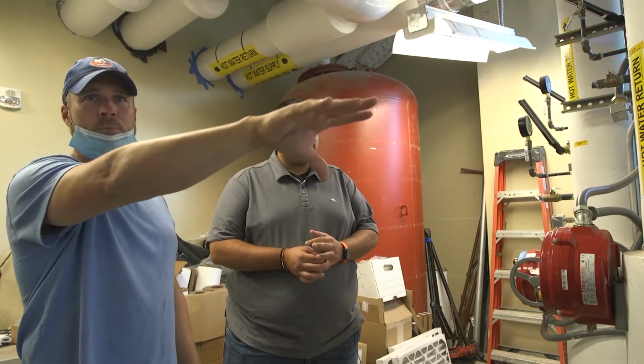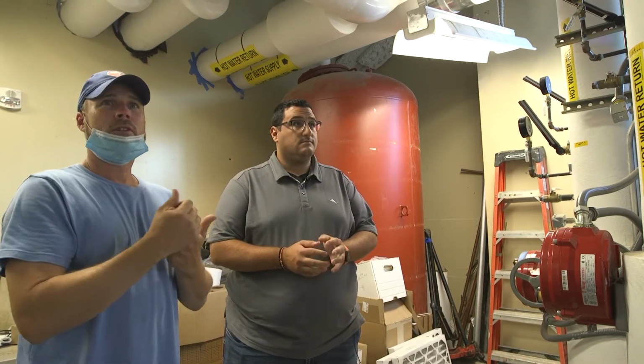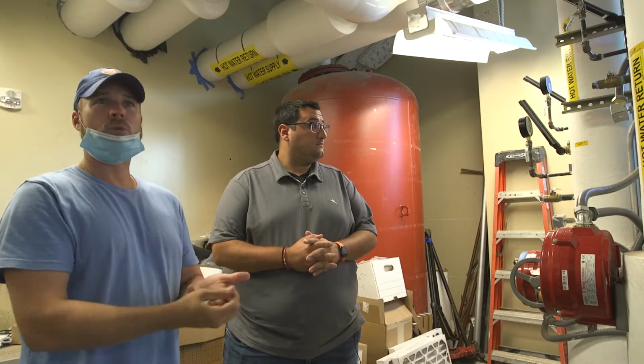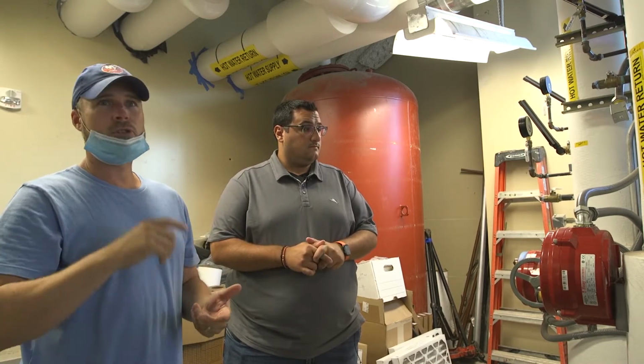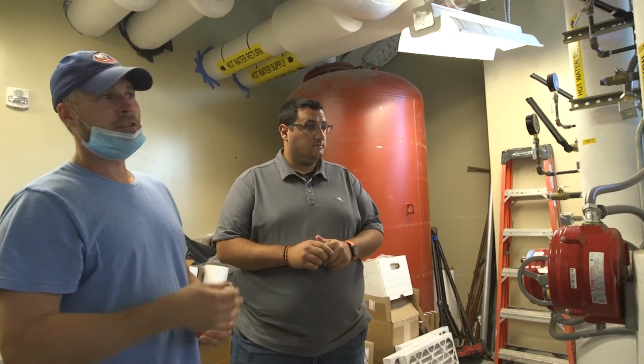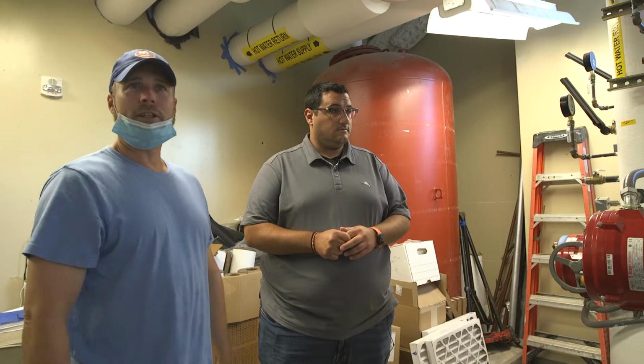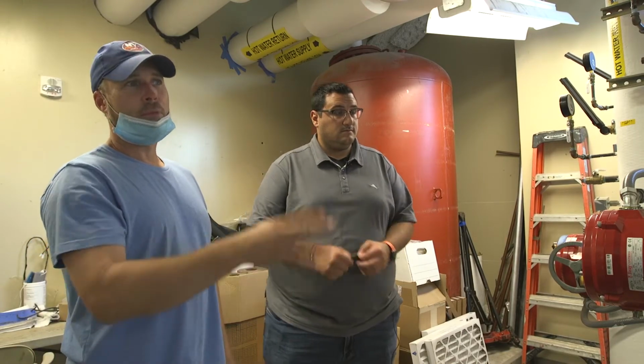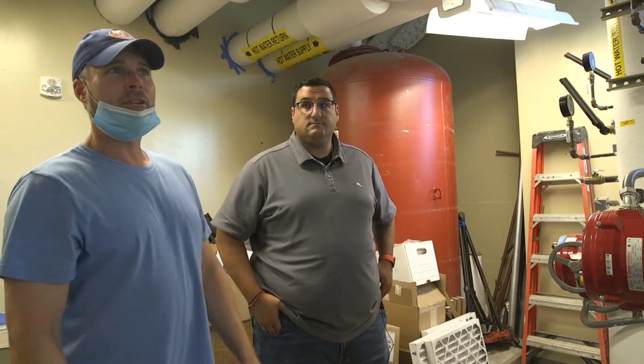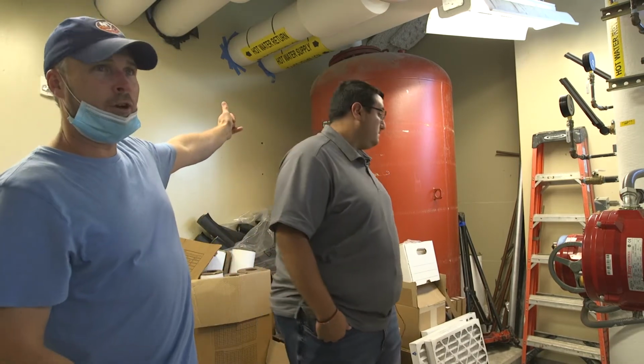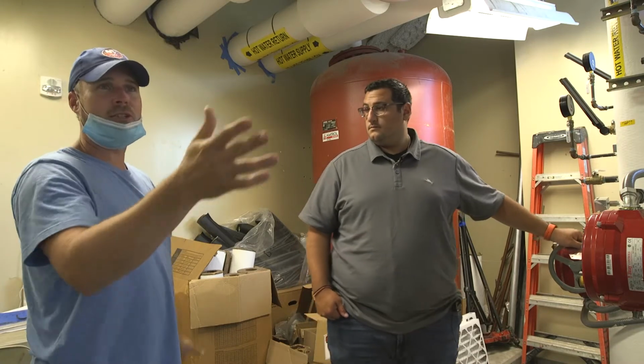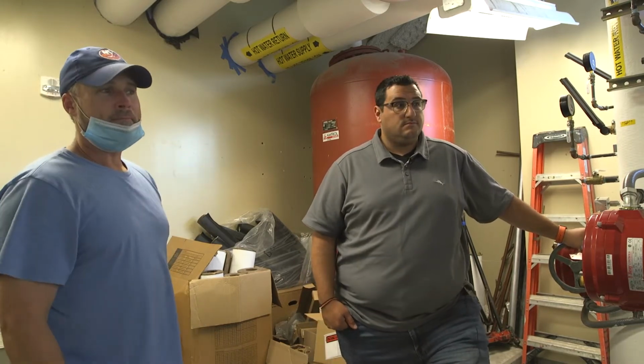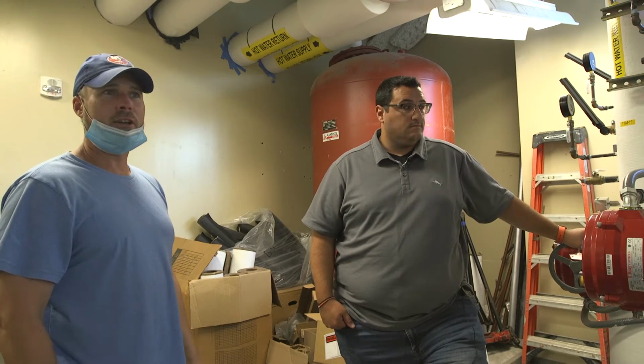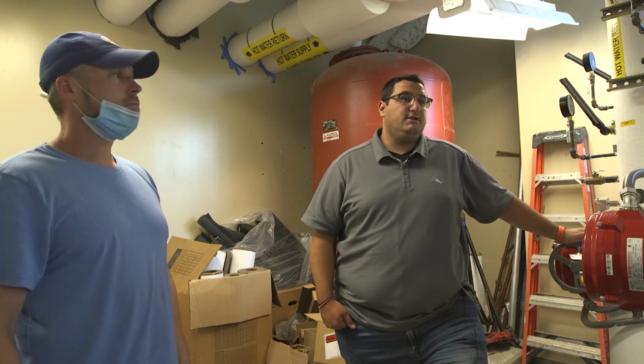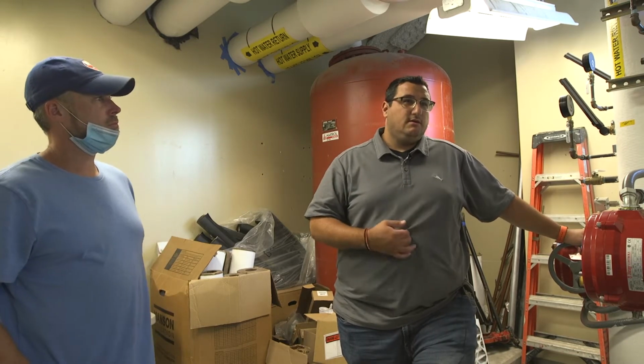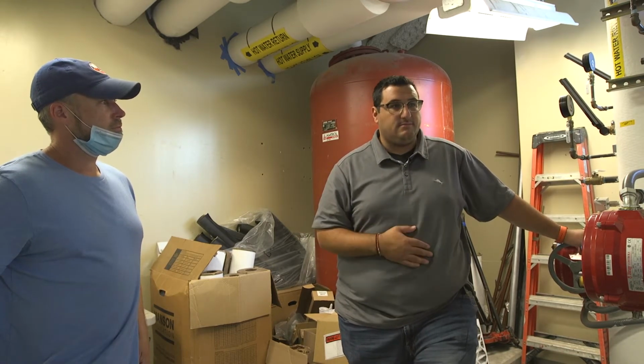Upstairs you have more of these pumps for your primary chilled water, your secondary chilled water, your condenser water, and your hot water. They're all the same pumps, all the same maintenance: greasing bearings, strainers, checking them occasionally. There's not much to the system. The pressures you're seeing in here are pretty much accurate. 50 pounds was the fill pressure. That's the set on the makeup water tanks. The expansion tanks, that's pretty much all you're looking at on the pumping systems. You really just want to be on the lookout for any unusual noise, any gauge fluctuations, that kind of stuff. Other than that, you're okay.